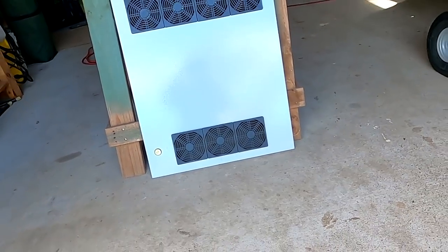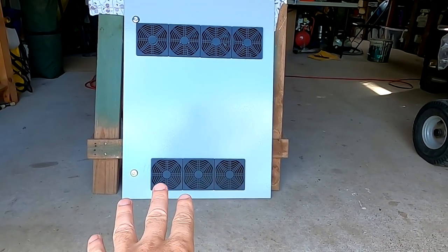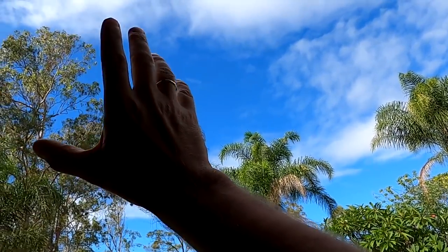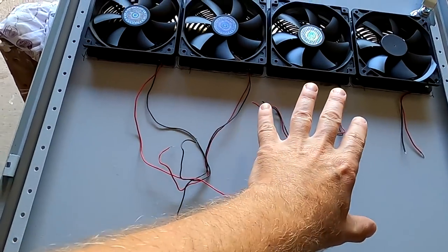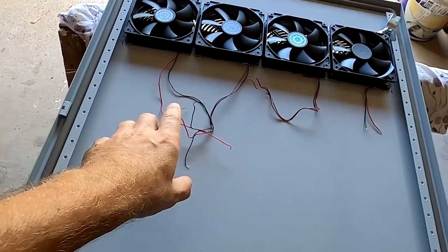This is how the whole door looks like - four fans at the top sucking air out of the enclosure, and three inlets with dust filters at the bottom sucking cool fresh air in. It is cooler - we've got autumn now and you can see blue sunny sky. The next step will be to cable all this and get it installed.